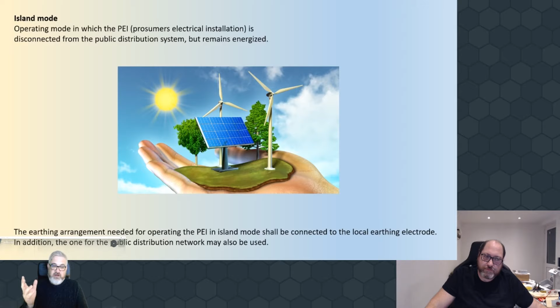I've seen island referenced a few times with common earthing systems. If you go back to the 16th edition, Amendment 3, there was a section on generators or other sources, with a reference to switching out of the DNO earthing if you had an alternative power source. On the underground, we had a 30 kVA UPS, and if there was a DNO power loss while that power was being generated within the station, you'd get a certain amount of leakage current. One requirement was to switch out that earth so you couldn't potentially injure people working on the supply cable.